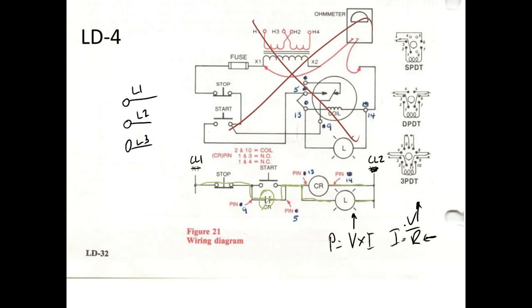So if you plug this thing over L1 and L2 on 3-phase and press that button, your relay would blow up just like that, and the light bulb would blow too. That's why I'm not calling our control circuit L1 and L2 - I'm calling it CL1 and CL2. None of our control circuits are going to hook up to 3-phase L1 and 3-phase L2. They're going to hook up to our L1 and L2, which is on the other side of our divided-by-2 transformer. You understand?